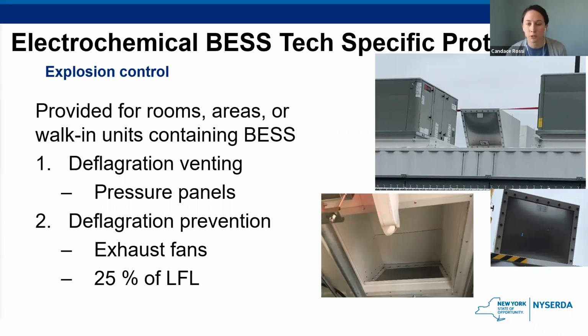And then the other requirement that they can do is the deflagration prevention. This can be done using exhaust fans and limiting the lower flammability limit to 25%. This is a requirement where we will see developers put exhaust vents and fans in their lithium ion systems. So like I said, while lithium ion is not required to have exhaust ventilation as part of the other 2 requirements that would require it, they can utilize that as part of their explosion control requirements. And I will say, I think the majority of the time they are putting those in.